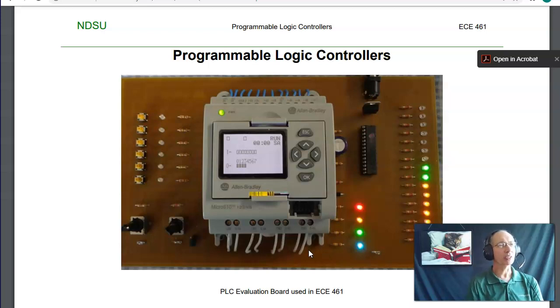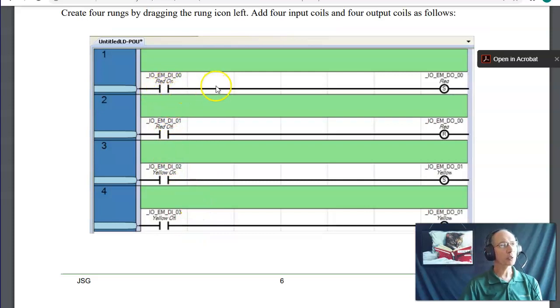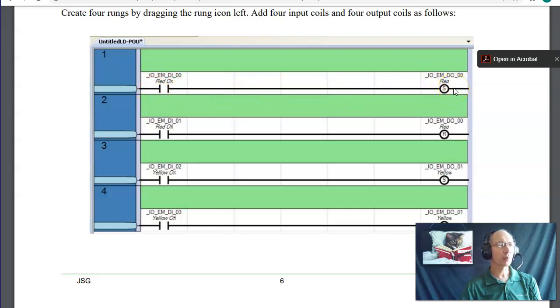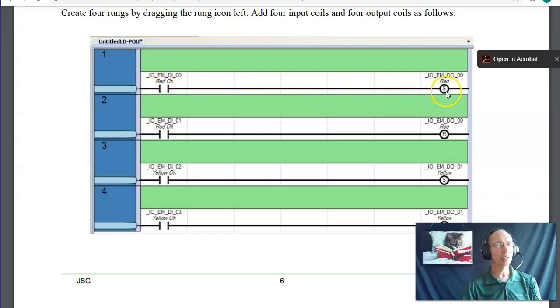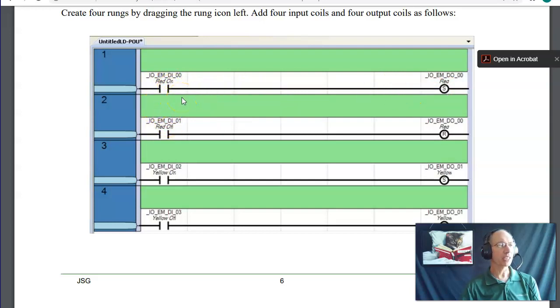We're going to start out with PLCs. PLCs are oftentimes programmed with a thing called Ladder Logic. It's a graphical version of a programming language. It's got these switches — if this switch is closed, then a light turns on. I can put switches in series and have switch 1 AND switch 2 turn on the light. If they're in parallel, switch 1 OR switch 2 turns the light on. There's also NOT, and given AND and NOT, you can do anything.